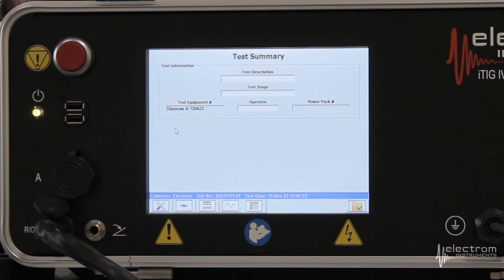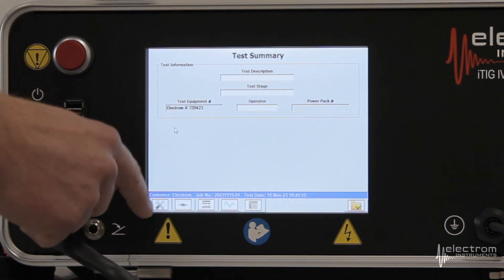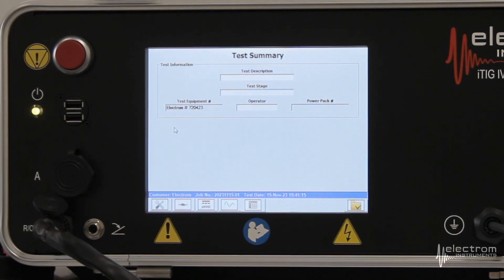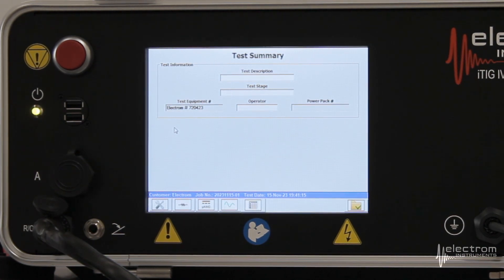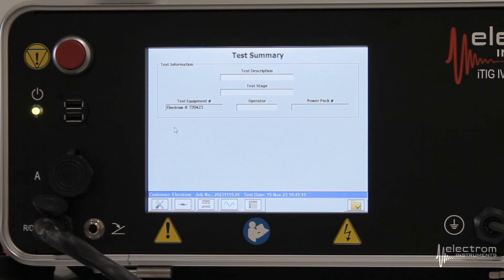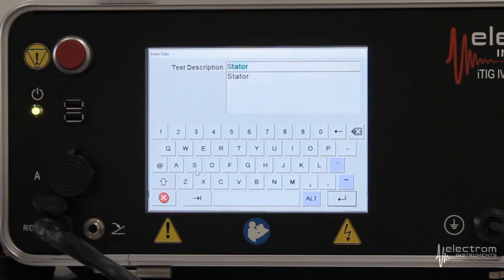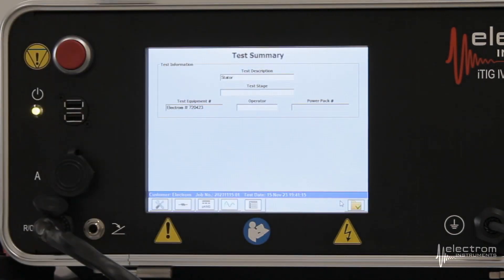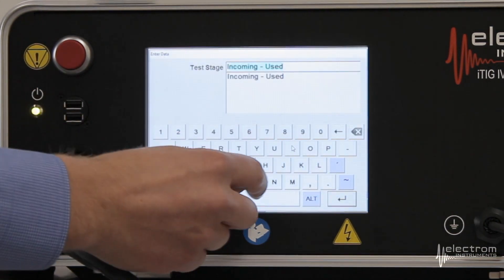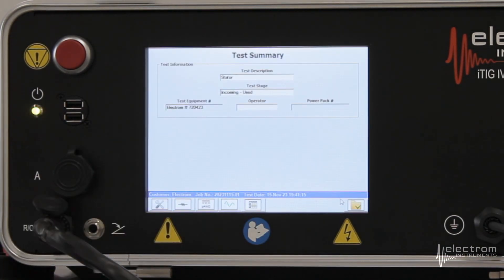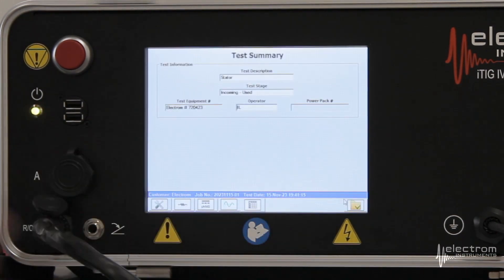We select Test. We are now in test mode and we'll work our way from left to right along the tabs at the bottom of the screen. We're currently on the last tab, the test summary screen. This is where we will get the pass-fail recommendations at the end of the test set. There are three optional fields here that are nice to use from a reporting perspective: a test description field — in this case, a stator as opposed to an assembled motor — a test stage to identify where you are in the service process, and the operator, where I like to use my initials.